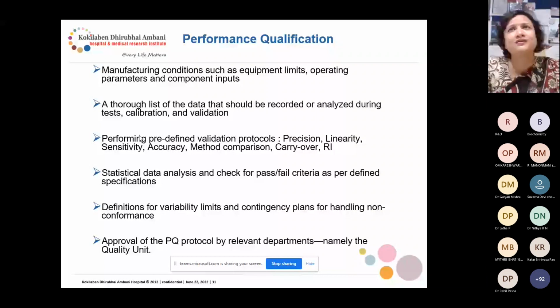I said, no, but we actually enrolled for that, and then we did the accuracy, precision check, reference interval check, everything. So I don't need that, because we have enrolled for linearity surveys. So then I got deficiencies, because before reporting patient results, I had not done any AMR verification or linearity. So this is one of the criteria to do the performance qualification.